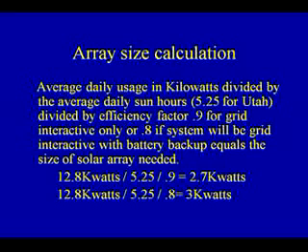For a battery backup system, 0.8 is the efficiency factor because batteries require more energy to be put into them than you can actually extract later for use. So they have a 10% loss in charging, as well as the efficiency factors we've talked about above.